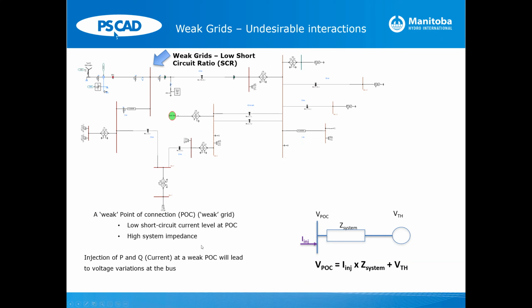So here is a system which is loosely based on the Australian power system. It's a very simplistic system. Here there was a request to have a wind farm connected to a point where the condition of this point of connection is extremely weak. What do we mean by weak? Well, here's an illustration. If you inject a small reactive current into the point of connection, you will see a very large change in voltage, okay?